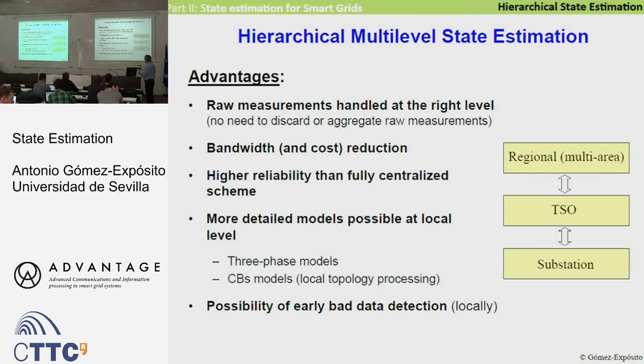We reduce the bandwidth, probably, and also the cost. This will be more reliable. And we can use a three-phase model at the substation, for instance, because there are three phases and each phase has its own measurement, which increases the redundancy. We can deal with topology errors locally, and we can probably detect bad data locally. So this is the advantage of processing as much information as possible here.